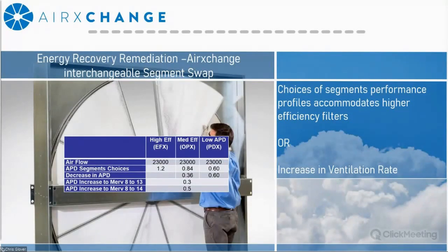So looking at the example on the left and starting with the high efficiency segment, if you were to move to a medium or lower efficiency segment, you gain about 0.36 inches worth of pressure drop, which can be used to either move more air if you're not changing anything to the fan system, or increase filtration, as you can see from the transition from MERV 8 to MERV 13, which is roughly the same decrease that you're getting from the segment swap. If going from the high efficiency segment to a low pressure drop segment, it gives you even more allowance, so you might be able to achieve a little bit of both.